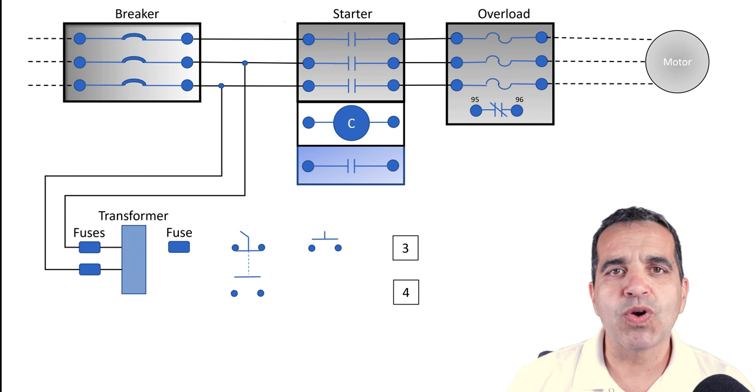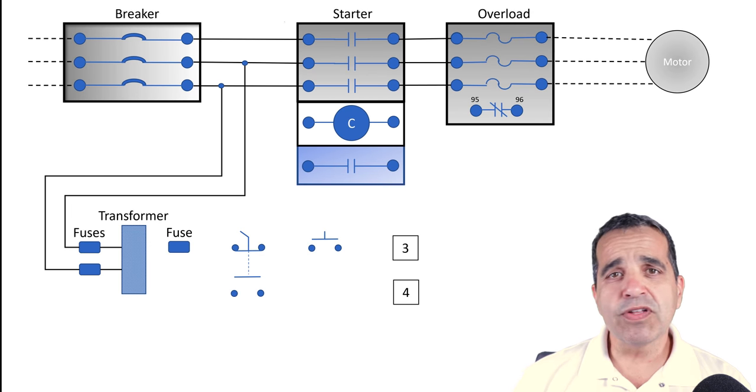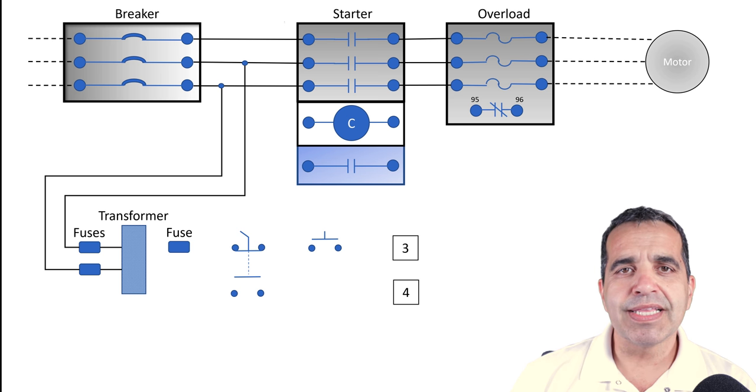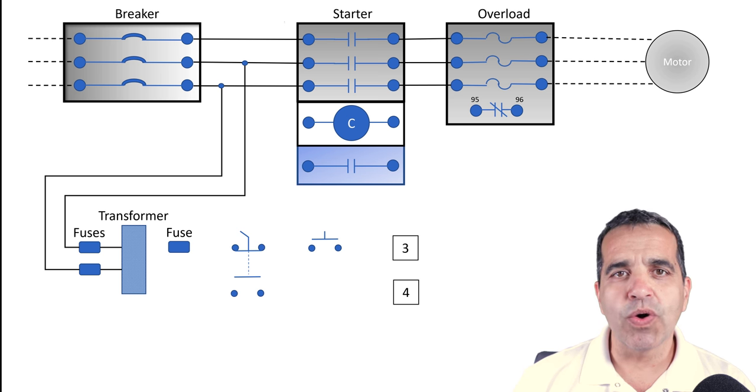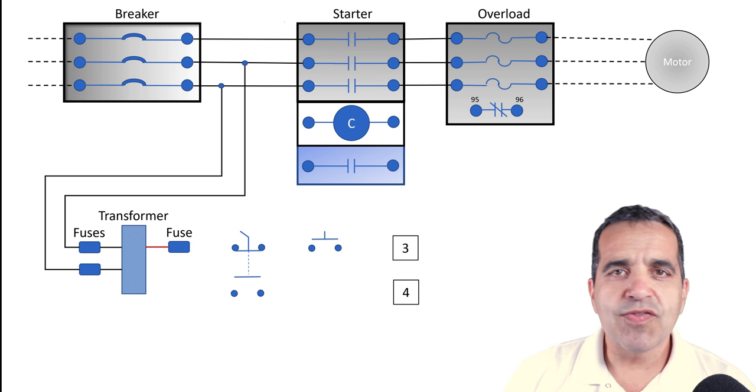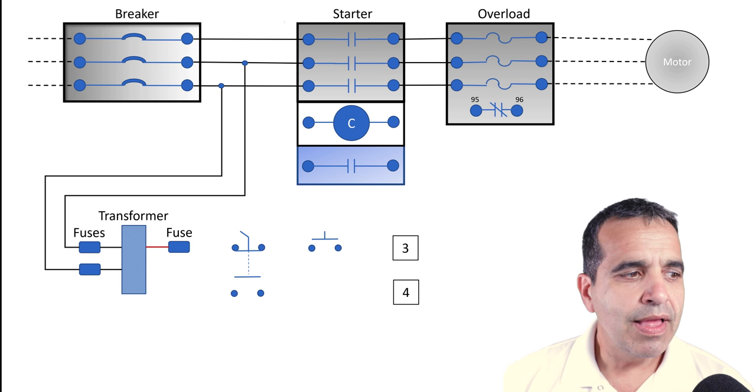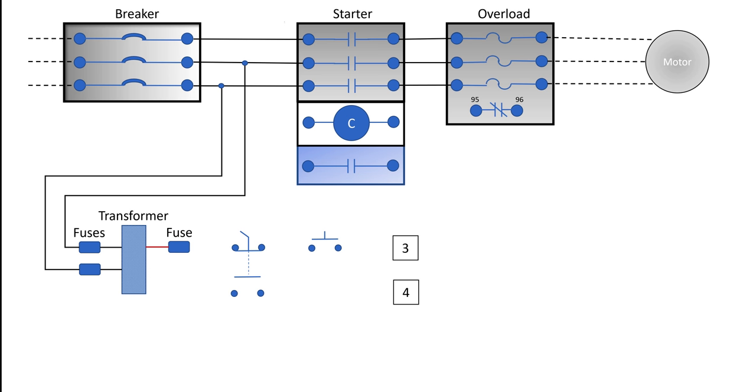We're going to use that 120 volts control power for our coil or any field devices that we have, but ultimately that control power is feeding our coil. From the transformer, we feed our fuse and we also come from the transformer with our neutral. That neutral will feed our overload contact.